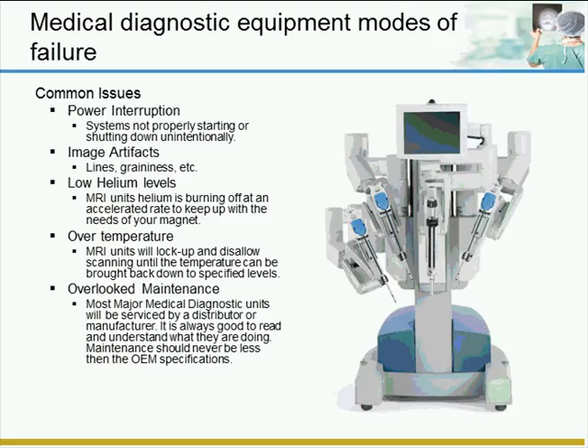We have a couple of common issues that we've seen with the medical equipment. Power outage: if your facility loses power, medical equipment goes down. Sometimes it will be due to a tripped breaker. You want to make sure that all dedicated circuits, all the breakers, are properly functioning and in the on position.